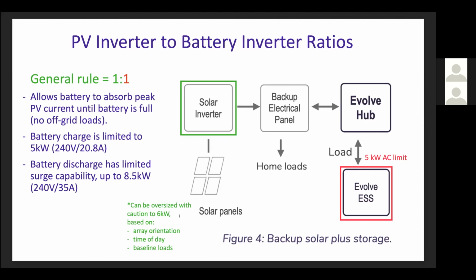Okay, real quick, PV inverter to battery inverter ratios. As a general rule, it's 1-to-1. This allows the battery to absorb peak PV current until the battery is full, given that there are no off-grid loads. The battery charge is limited to 5 kW, and so that's the reasoning behind not wanting to overdrive the battery inverter in off-grid mode.